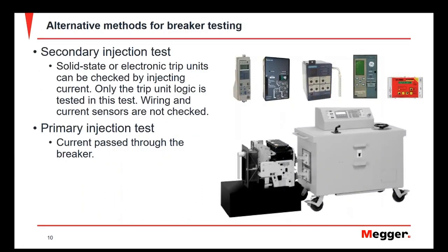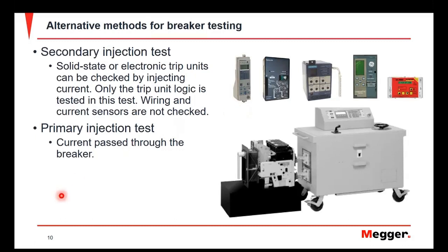Whenever we talk about primary current injection, there are always alternative methods mentioned, and we have to understand what we're talking about. One that always comes up is secondary injection. Secondary injection is a means of testing a circuit breaker that has a solid state or electronic trip unit. However, whenever we do that type of testing, that's the only part of the breaker we're really testing — those different manufacturers' electronic trip units.